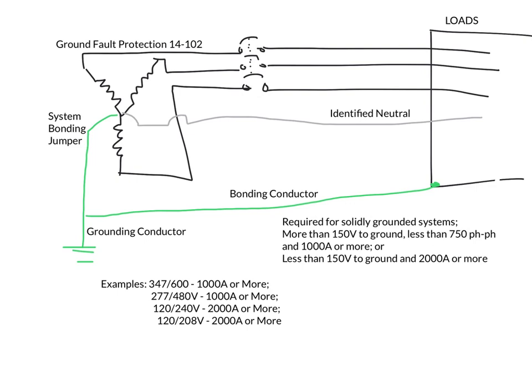We can also see this on single-phase systems, 120/240 at 2,000 amps or more, or on lower voltage three-phase systems, 120/208 volt systems at 2,000 amps or more. Now, those systems aren't terribly common. We do come across them occasionally in rural areas where the utility can't supply us with a higher voltage. You're stuck with 240. But for the most part, I see these types of systems on 347/600 type systems at 1,000 amps or more. It's fairly common in light industrial and some commercial applications.